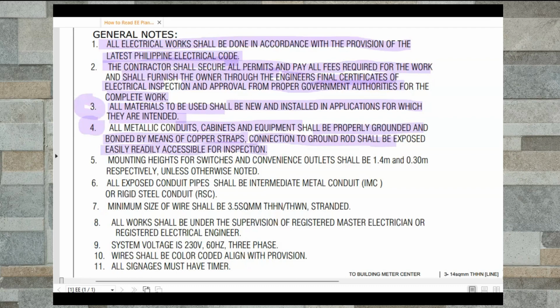Remember that. Number 5: mounting heights for switches and convenience outlets shall be 1.4 meters and 0.3 meters respectively, unless otherwise noted. Meaning switches should be mounted at a height of 1.4 meters, and outlets at 0.3 meters. But this height is still subject to verification by the project architect.